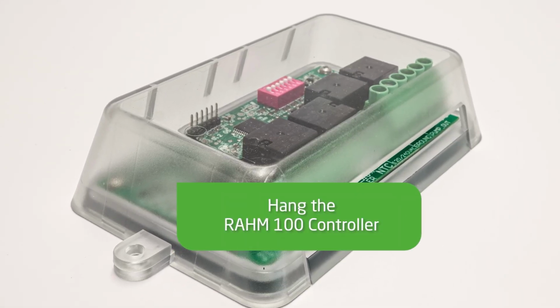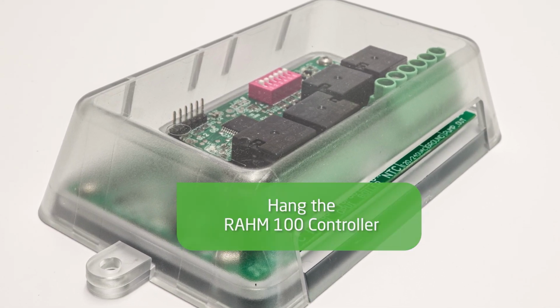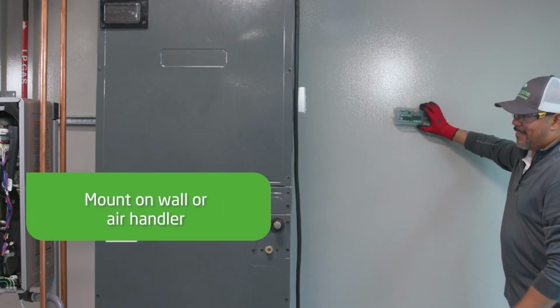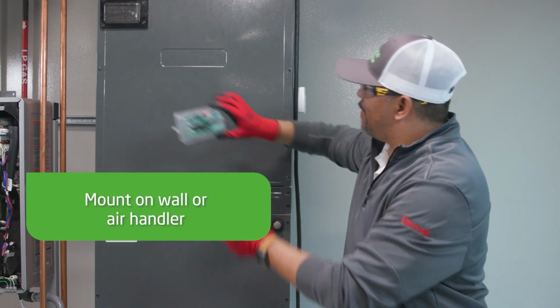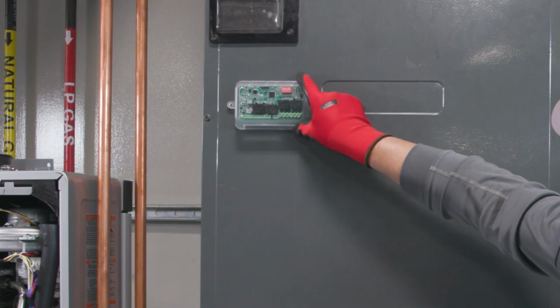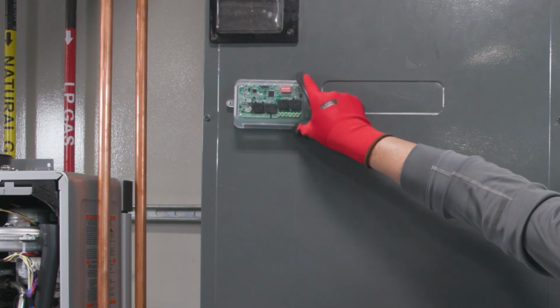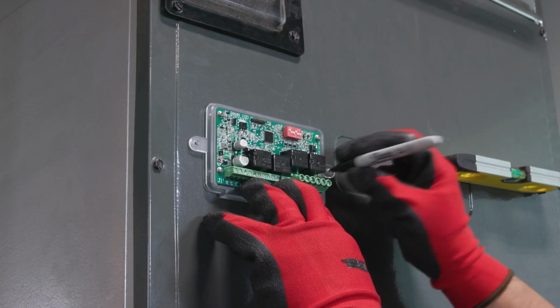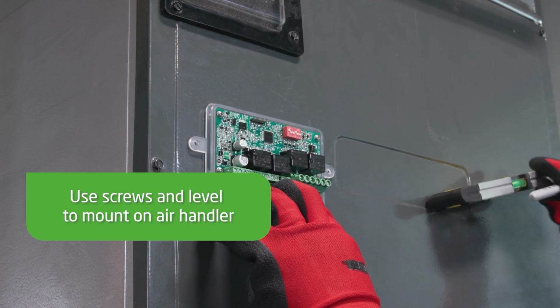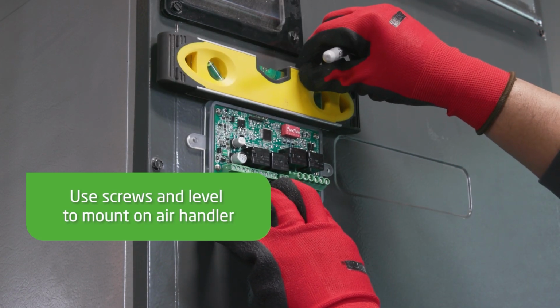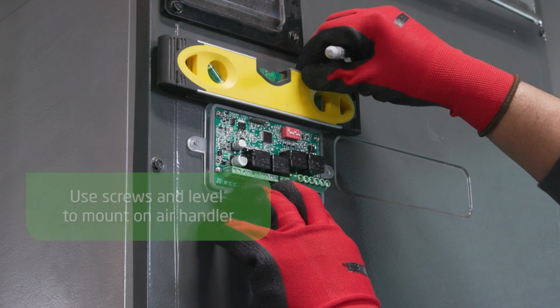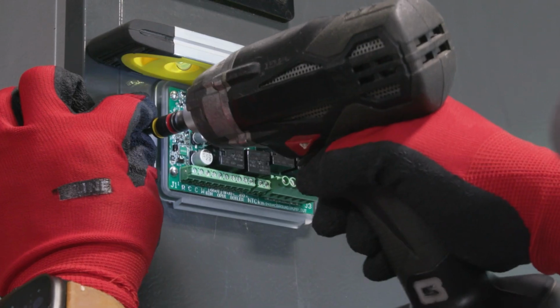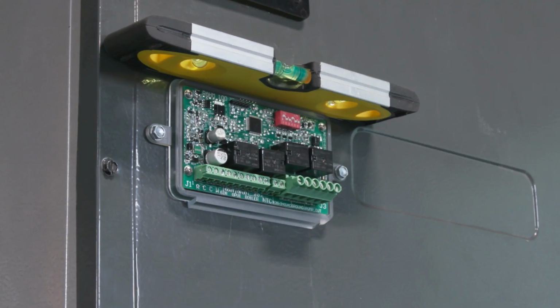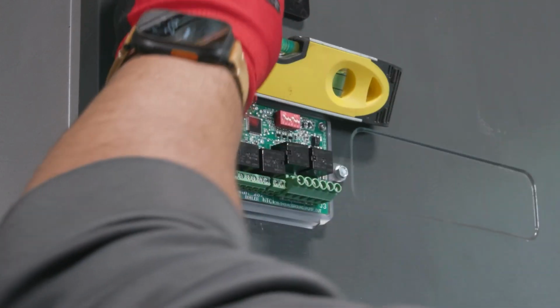Now we will hang the RAHM 100 controller, which can be mounted on the wall or on the air handler. Make sure the wall can support the weight of the controller and any other components needed. If you're installing on the air handler itself, use appropriate screws such as zip screws. You're going to want to use a level for this to make sure it's straight. Then use a driver to mount the controller.